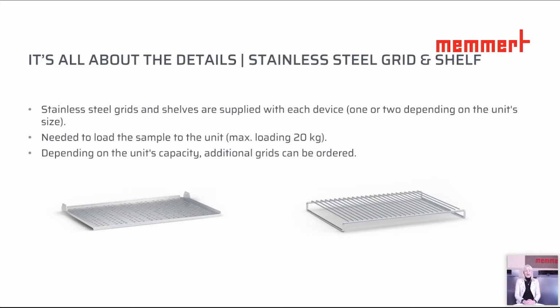Please kindly consider that in the standard delivery execution, one grid is always included, for example for the sizes 30 and 55, or two grids for the taller sizes. Additional grids are available as an option, and for example, when we consider the very common model size 750, there is the possibility to place up to 14 grids. The grids have the advantage that you have very good uniformity in the interior, because the air can pass through the different bars.